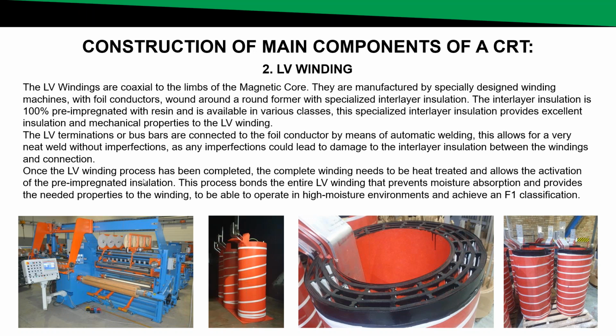Once the LV winding process has been completed, the complete winding needs to be heat treated, which allows for the activation of the pre-impregnated insulation. This process bonds the entire LV winding, which prevents moisture absorption and provides the needed properties to the winding to be able to operate in high moisture environments and achieve an F1 classification.